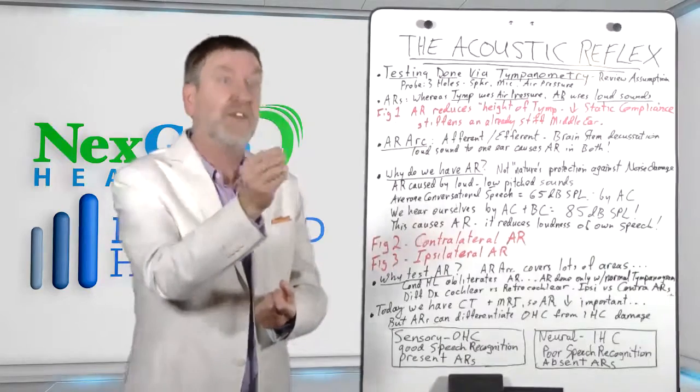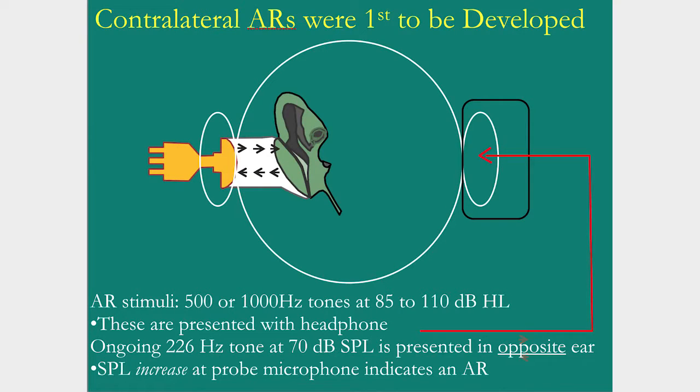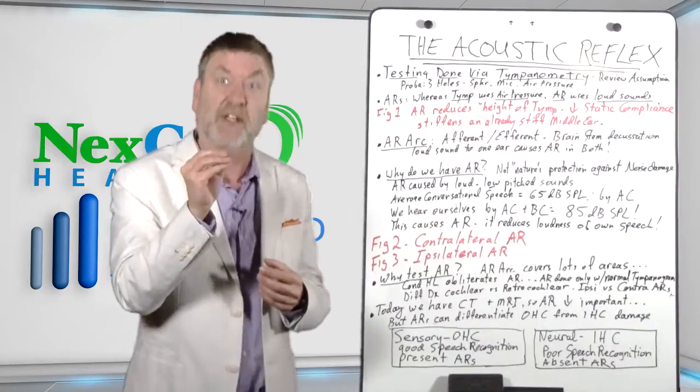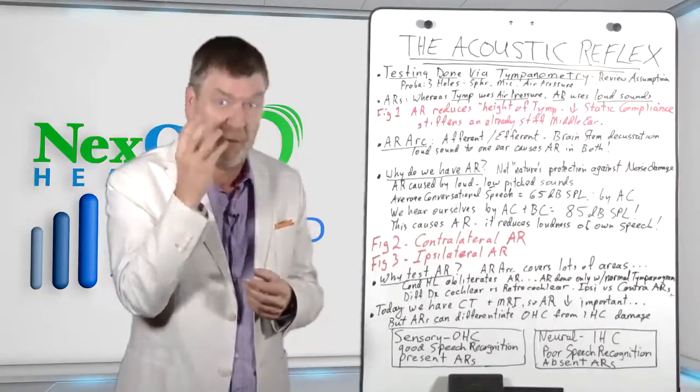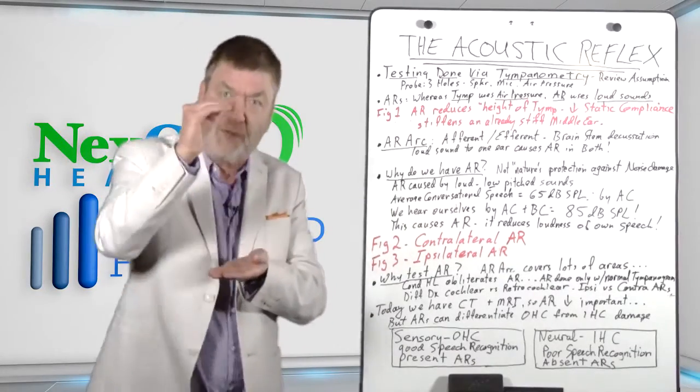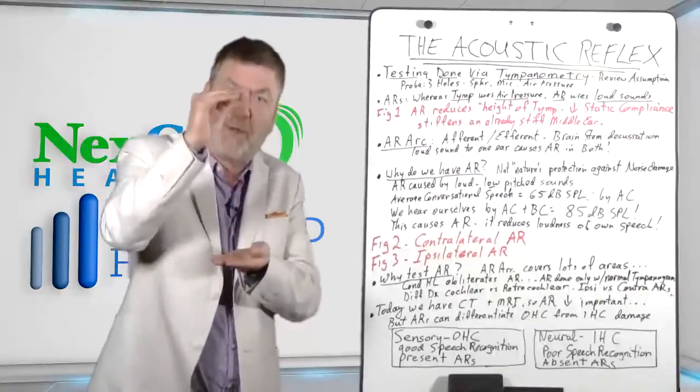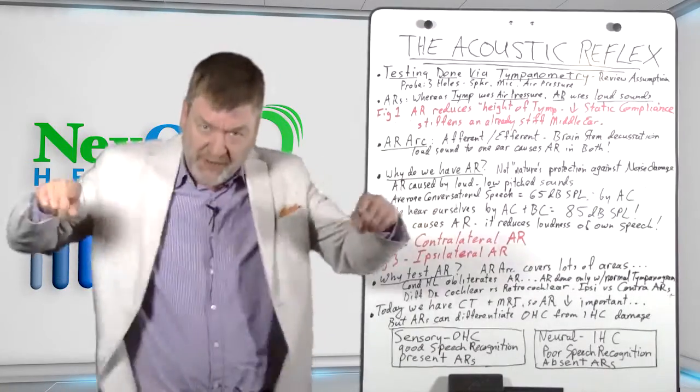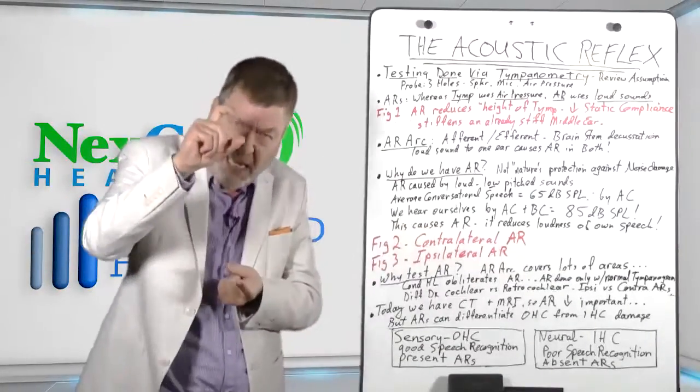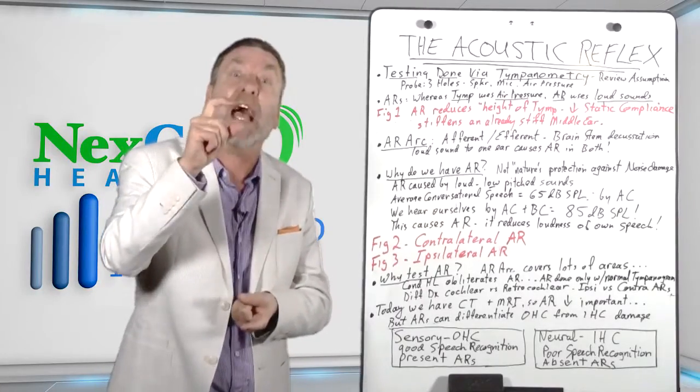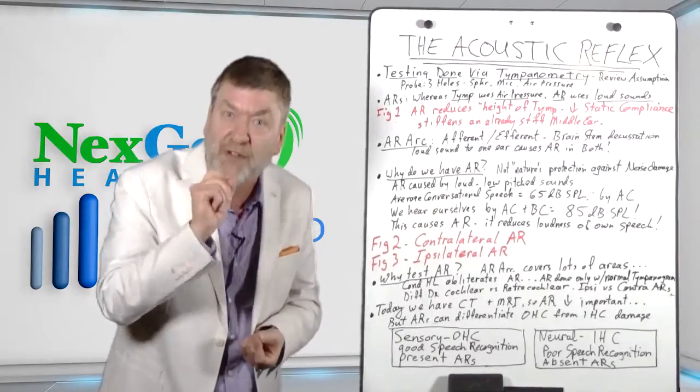Therefore reducing the efficiency temporarily of the sound transmission through that conductive middle ear system. When that happens, there's a change in the amount of sound bouncing back off of the probe tone. So a loud sound here alters the amount of sound bouncing off the eardrum. Actually, it increases the amount of sound bouncing off the eardrum, therefore reducing the efficiency of this middle ear for a split second. And that reduction in tympanogram size, that reduction in static compliance in the height of the tympanogram, that is what is measured as the acoustic reflex.